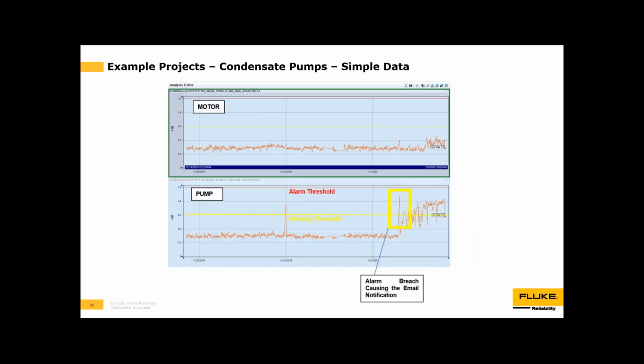The next step was looking at these trends and setting some alarms. Fortunately, in this circumstance we have a very unique graph with defined values and a clean correlation. There was a breach of this vibration level—it went right through the warning. There was an earlier breach as well.